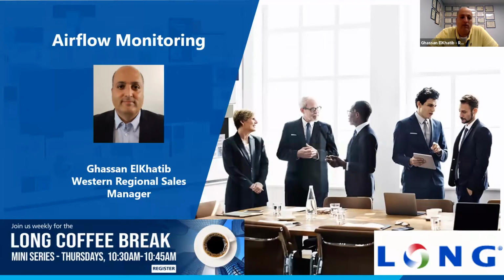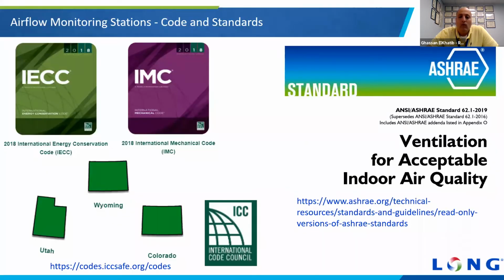With that, we'll go ahead and start through the airflow monitoring. So why do we need it? It's a code requirement to maintain the ventilation. Now more than ever, we also need to make sure that we're getting the right amount of outdoor air into the building to make sure it's a healthy environment. Utah and many other states have adopted the International Code Council codes. So we look at the International Mechanical Code and the International Energy Conservation Code. Currently we're at 2018. 2021 is going to be adopted very soon. It has very similar language as far as the airflow monitoring.